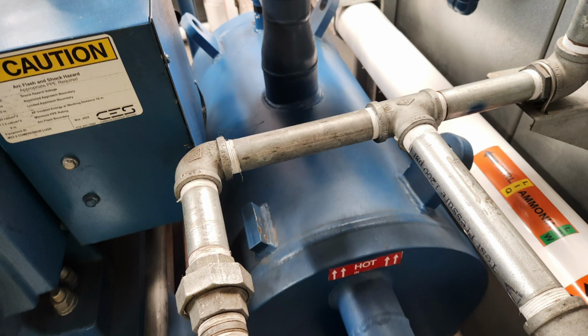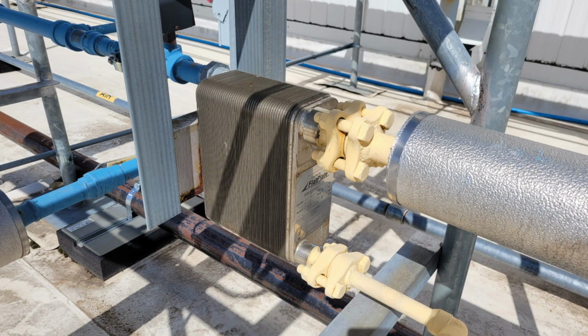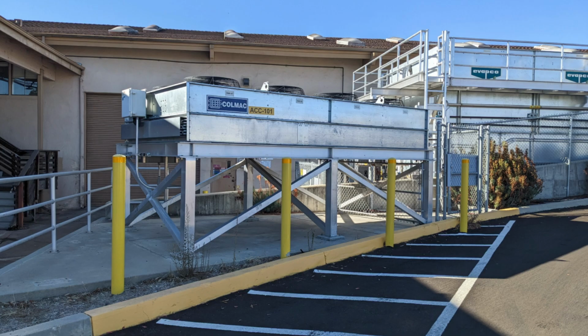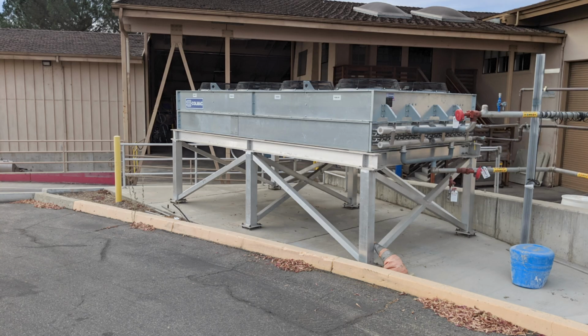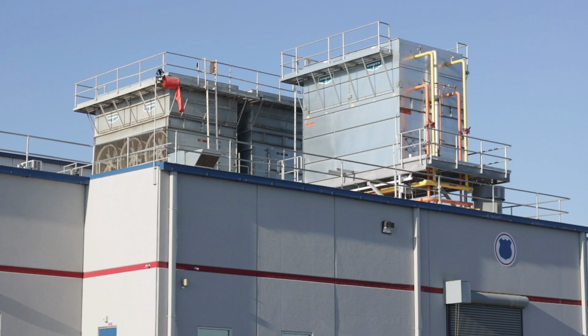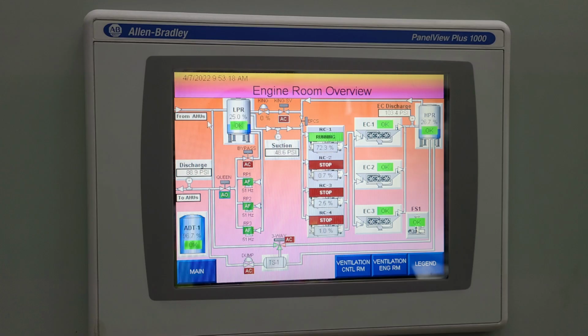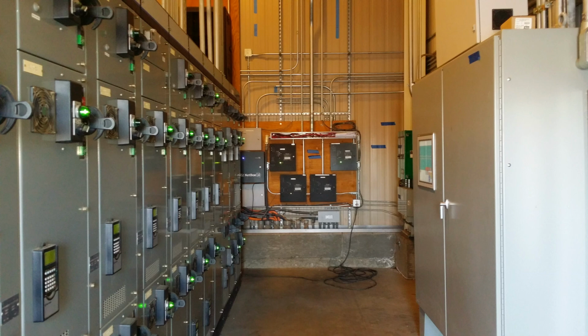Water-cooled condensers are started similarly, except the steps related to water chemistry and fans are associated with a remote cooling tower instead of the condenser itself. Air-cooled condensers do not have water, so no water treatment, sump level, or starting of pumps is necessary. Typically, condensers are shut down at the PLC HMI. Individual fan or pump motors can be shut off at the electrical disconnect on the MCC panel.